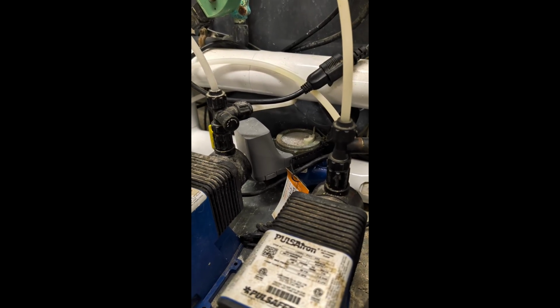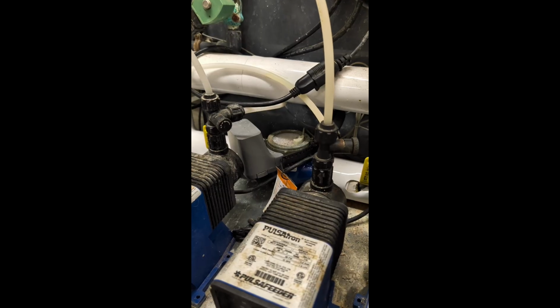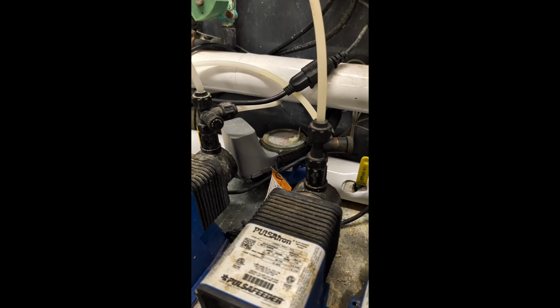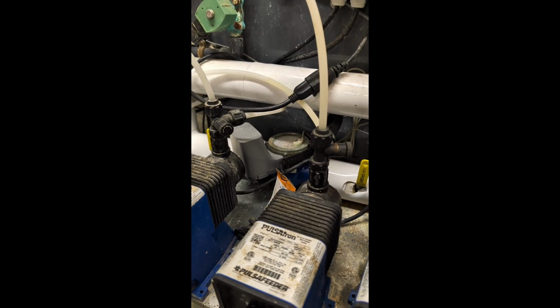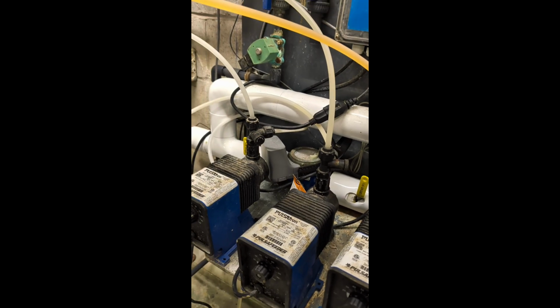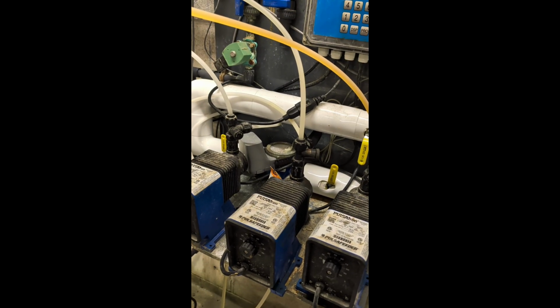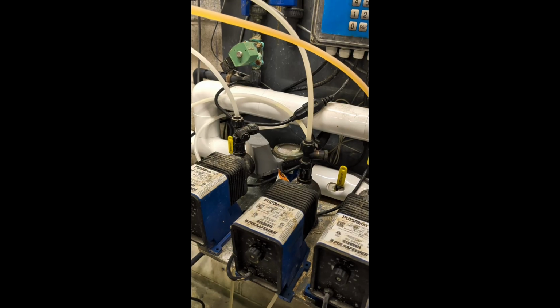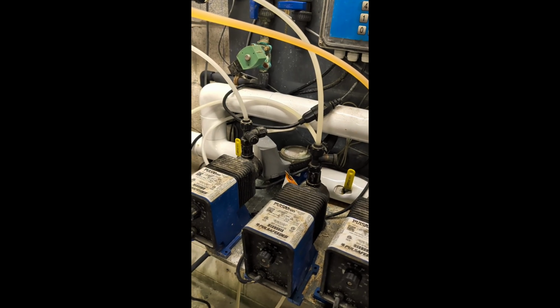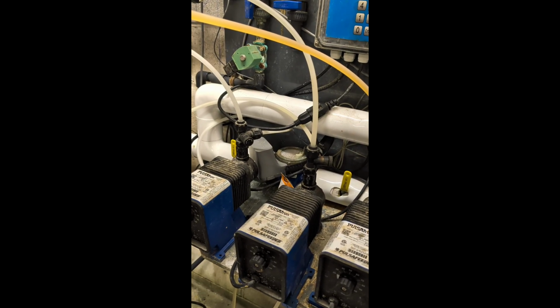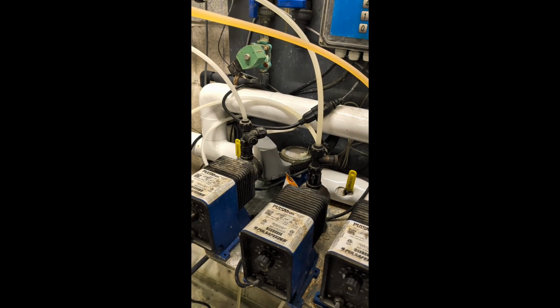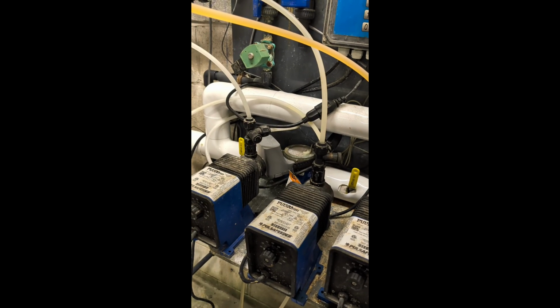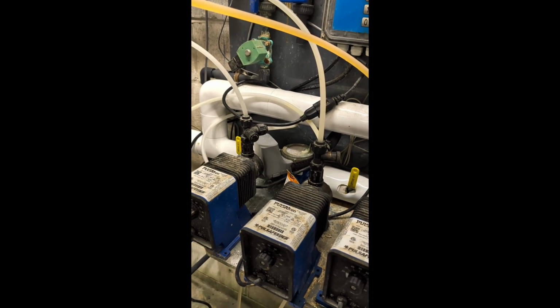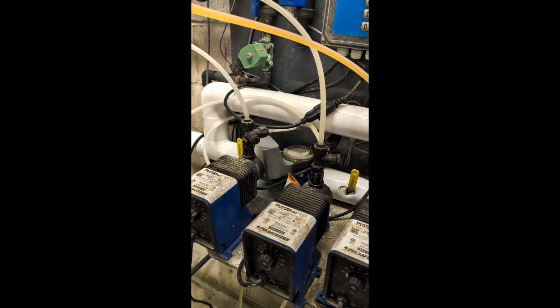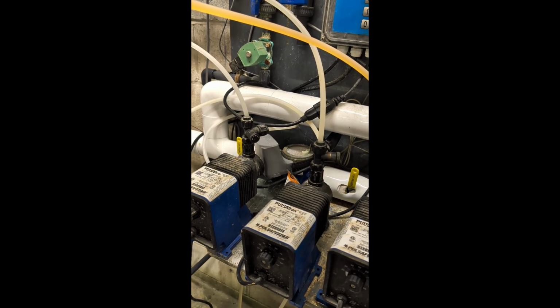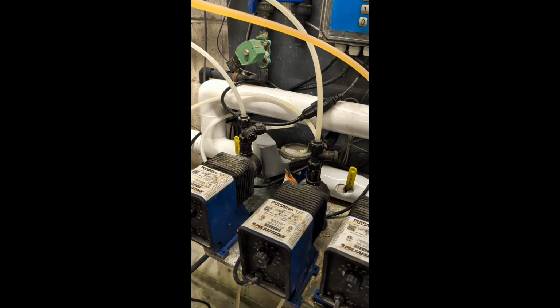Now, this particular water meter is for the water that feeds our cooling tower, which is a significant use of water in the summer. There's another identical one downstairs in the basement on the main water meter that comes into the building. Now, these units monitor minute by minute the flow through the water meters. There's nothing complicated. There's a rubber strap that they strap around the side. There's a couple of D-cell batteries in them that last for 2 or 3 years. There's no wiring, no plumbing needed, so they're really easy to install and add.